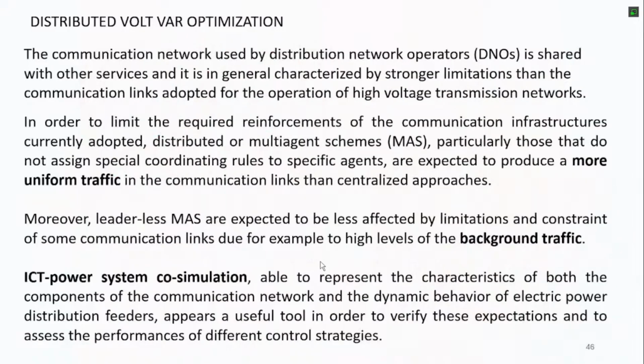So the distributed voltage and reactive power optimization, which I will call VVO. The communication network used by these distribution system operators, in general, is a shared communication network, so it is not based directly on all the fiber links that are instead used by the transmission operators. In general, for the distribution networks, the network used for communication is less reliable, efficient, or private than that of the transmission network. So in general, it is the common communication for cellular phones and so on.